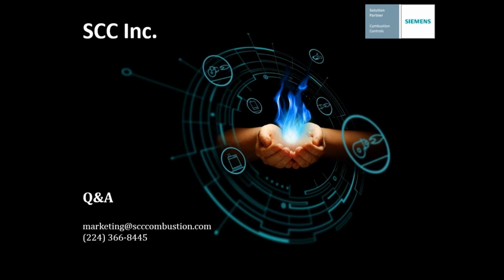Okay, very good. Another one that came in is, can you talk about 2 fuel curves in an LMV36? Like, how are those used and how might they be used? 2 fuel curves is great. The benefit of the LMV3 on the fuel curves is, first of all, when you go to make 2 curves, you can make them gas for propane, gas 0, and then gas for natural gas, which would be like gas 1. So you can make both of the labels on the screen say gas, just gas 0 and gas 1.